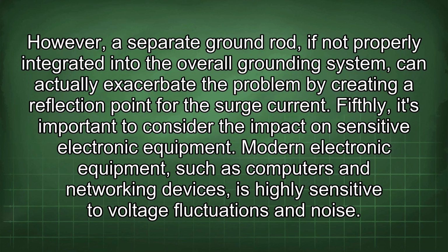However, a separate ground rod, if not properly integrated into the overall grounding system, can actually exacerbate the problem by creating a reflection point for the surge current.